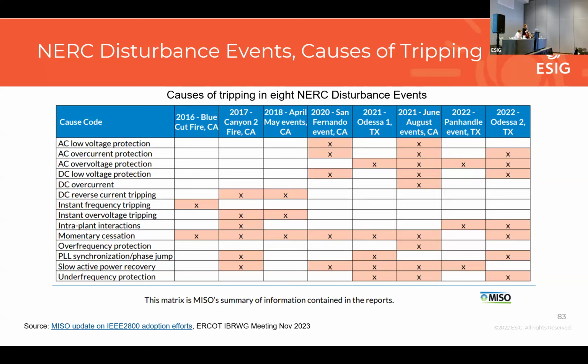So momentary cessation, slow active power recovery after the fault got cleared, AC overvoltage protection tripping IBRs. And this is because of reactive current injection that is too aggressive after the fault is cleared. It's not removed fast enough and results in overvoltage and then tripping of IBRs. So all of these things have been commonly happening since 2016 through 2022, 2023.